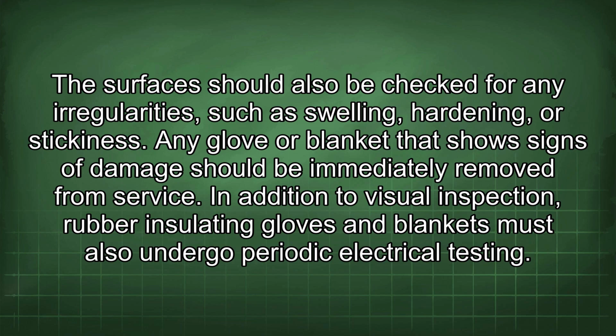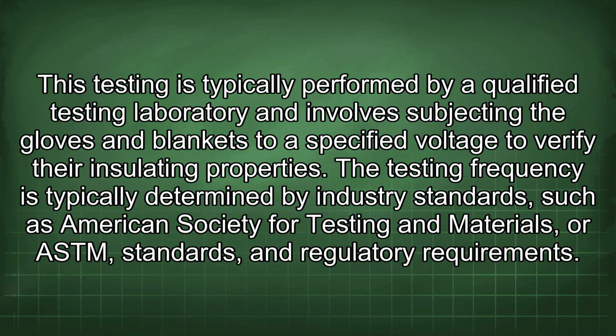In addition to visual inspection, rubber insulating gloves and blankets must also undergo periodic electrical testing. This testing is typically performed by a qualified testing laboratory and involves subjecting the gloves and blankets to a specified voltage to verify their insulating properties.